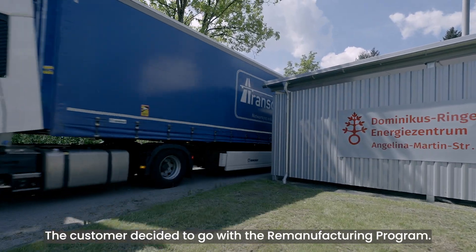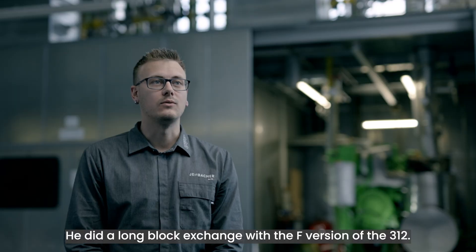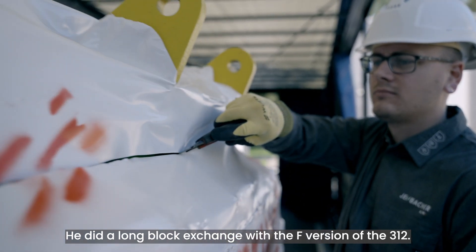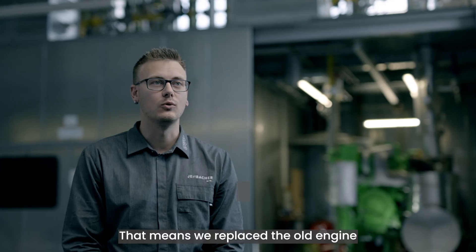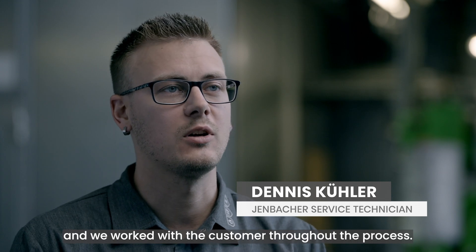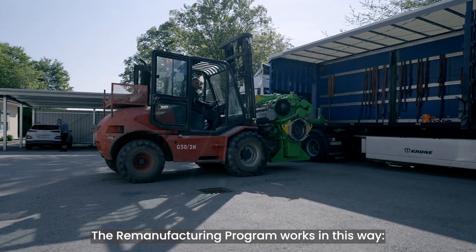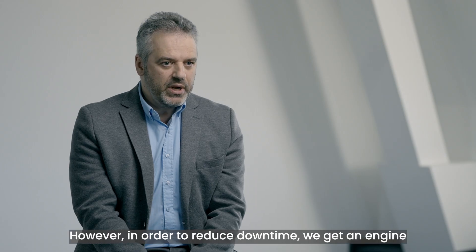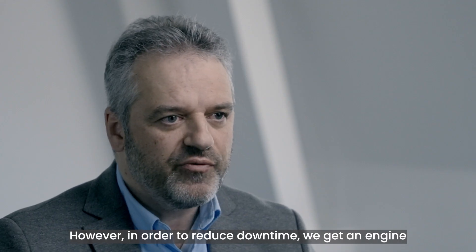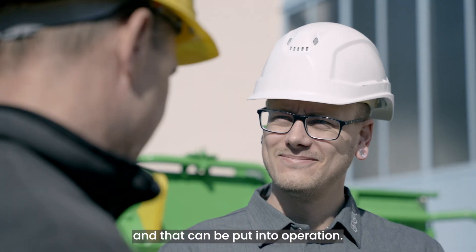The customer decided to go with the remanufacturing program. He did a long block exchange with the F-Version of the 312. That means we replaced the old engine at 60,000 hours and worked with the customer throughout the process. In order to reduce downtime, we get an engine that has already been overhauled and that can be put into operation.